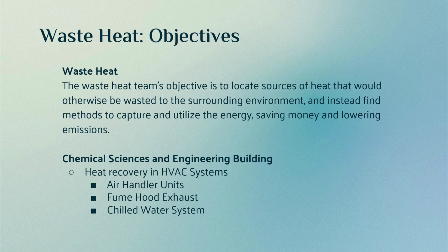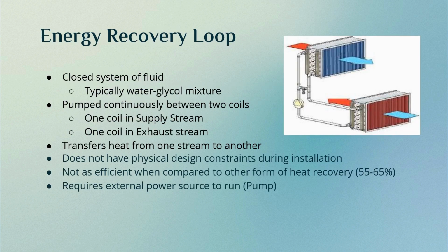carbon emissions. This year, we primarily focused on the chemical science and engineering building HVAC system, looking into sources of waste heat in their air handler units, fume hood exhaust, and chilled water systems. The first piece of air-to-air energy recovery equipment that we looked into was an energy recovery loop, which uses a closed system of a water glycol mixture pumped continuously between two coils in the supply and exhaust streams of the air handler units or exhaust fan systems.